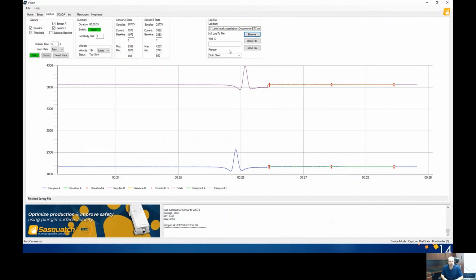But like I said, I want to encourage you to come in here and see how the sensor is working. This is a great tool, especially for commissioning the Sasquatch. When you want to make sure that you're getting clean waveforms, making sure that the plunger's arriving, and seeing some samples of the velocities you're getting. And then once this is set up, you flip over the connections to work with your RTU or your PLC or your plunger controller.